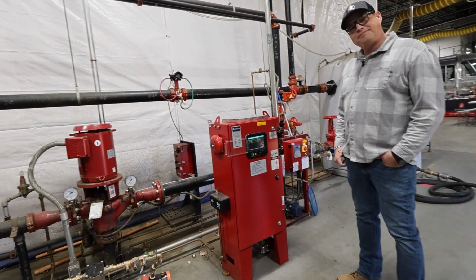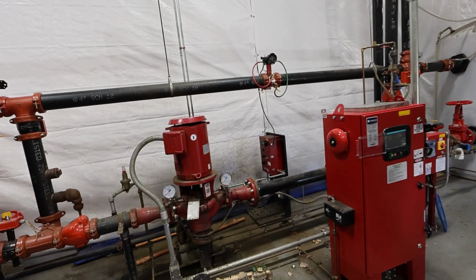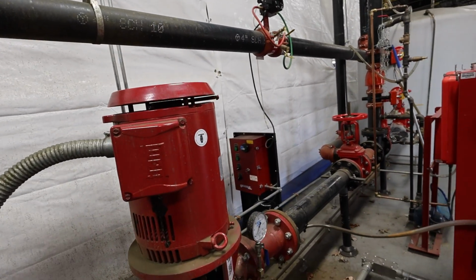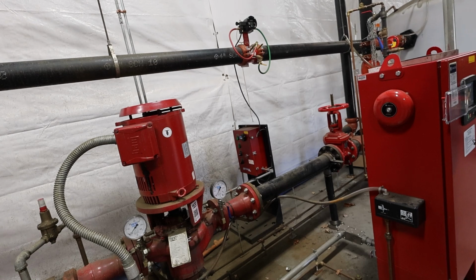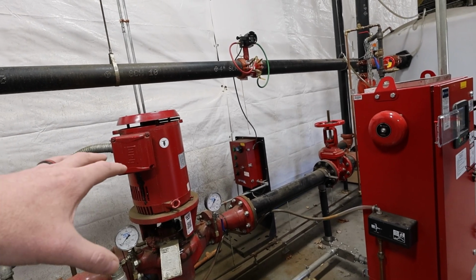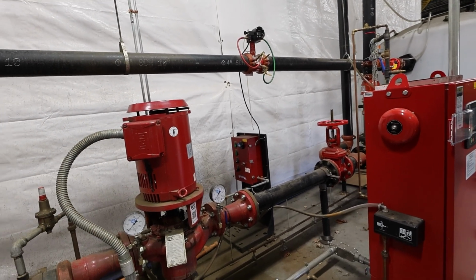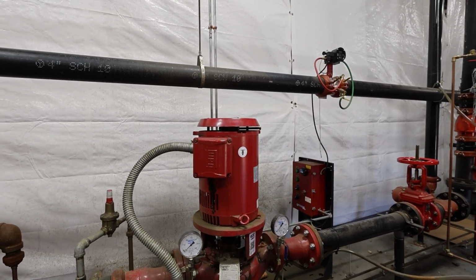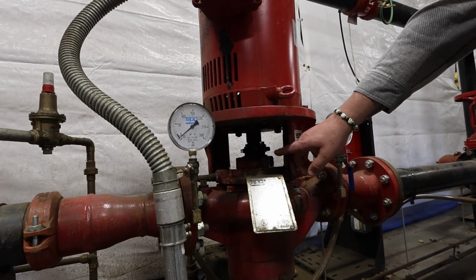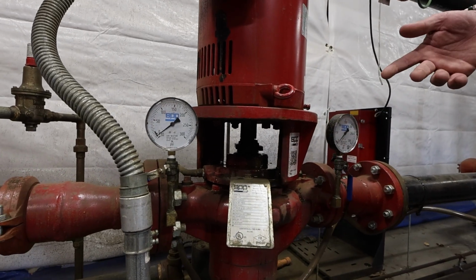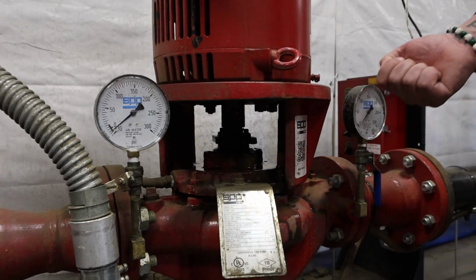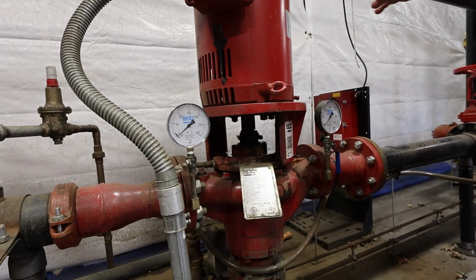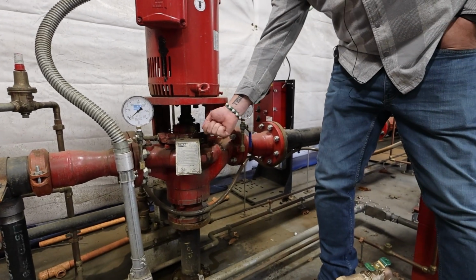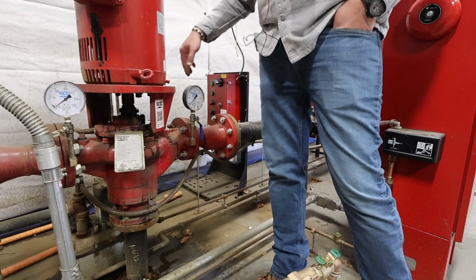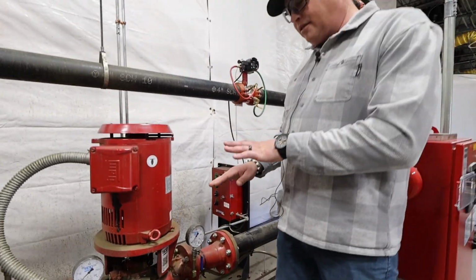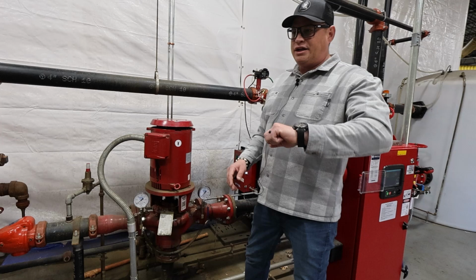Yeah. Now, this pump obviously has excessive leaking on here. Yes. It's seen better days. Yeah, horizontal split case pumps are a little bit easier to service. Is there a quick way to tighten the packing on a vertical inline pump? This is actually something I haven't done before. Yeah, I mean, you tighten your packing the same way you would on a horizontal split case. What I see a lot of people do is they'll go in and they'll just start ratcheting down on the packing gland instead of taking small movements on either side, even movements on either side, stepping back and letting the packing settle. You don't want to wrench down too hard on it.